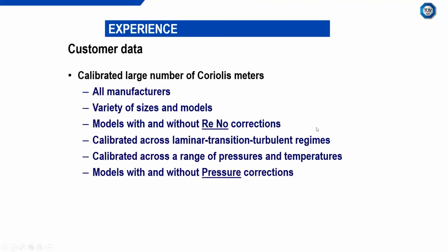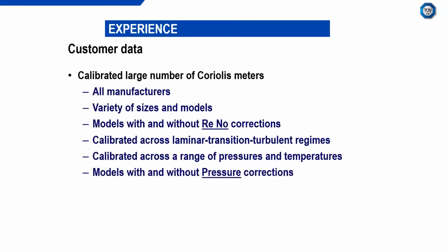Variety of sizes and models. Models with and without Reynolds number corrections. Some Coriolis manufacturers, or one in particular, have a patented Reynolds number correction. We've evaluated that device with and without the Reynolds number correction applied. We've calibrated across the laminar transition turbulent flow regime, across a range of pressures and temperatures, and we've also looked at the models with and without their pressure corrections applied.